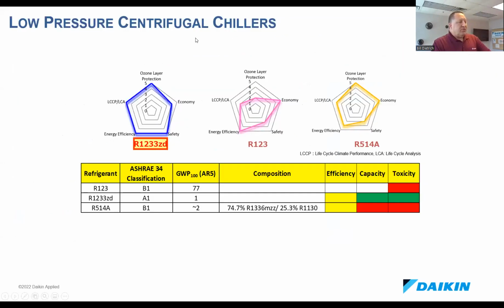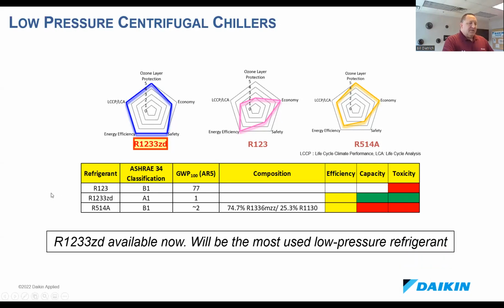On the low pressure centrifugals, we talked about this a little bit. Relative to the 123, the 1233 is about the same efficiency. You get more capacity, and now it's an A1. The 514A, again, is about the same efficiency, but you lose a bit of capacity, and it's still a B1. 1233 also has some nice properties as a foam agent and as a solvent. So I think we're going to see 1233 end up being like R11 used to be, as the main refrigerant used in lower pressure centrifugals.